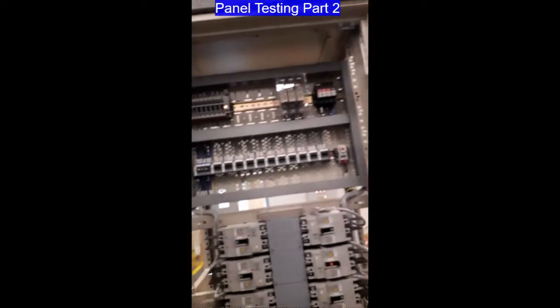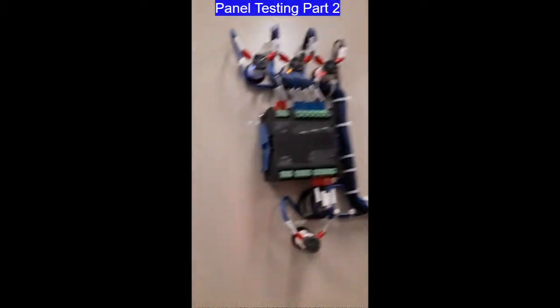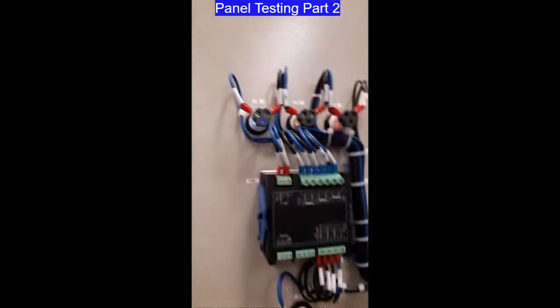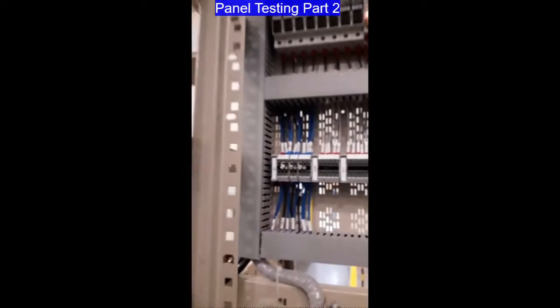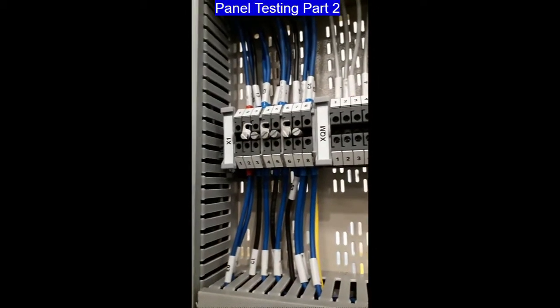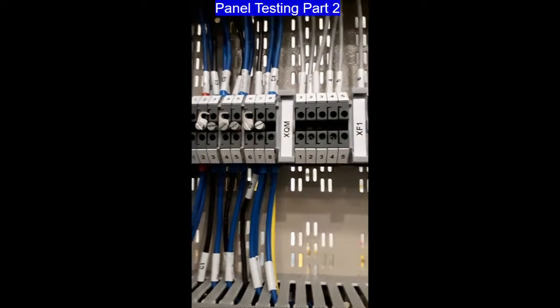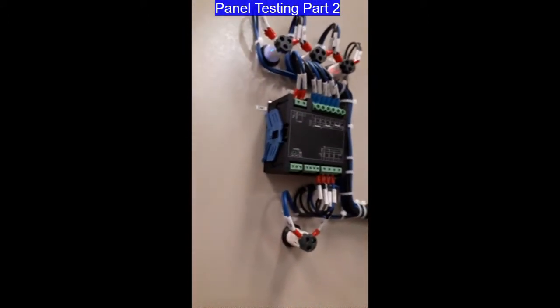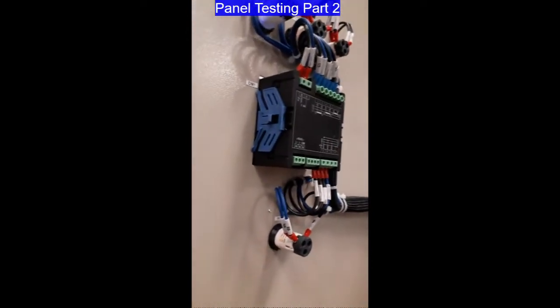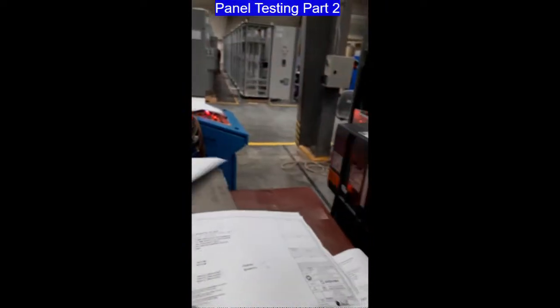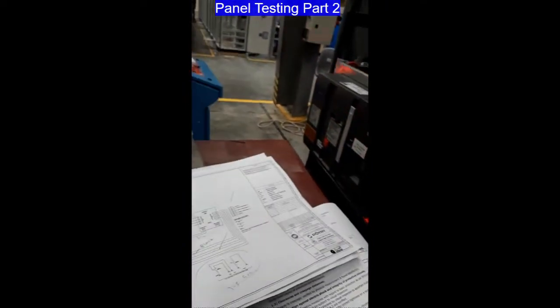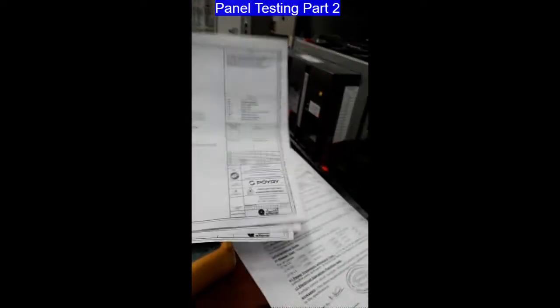All right, this is the wiring connection, and this is for the CT. Maybe you are asking why we have the shorting links inside. The use of the shorting links is to short the CT circuit in case the digital meter is removed or defective and needs to be replaced. You will also find in our drawing that it clearly mentions the shorting links are available in this area.